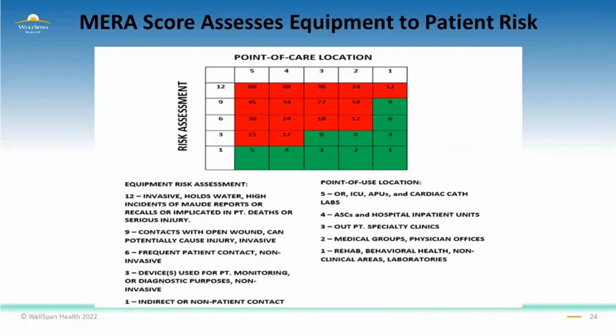We also know that the equipment is used in NICU, so we assign the location risk number as a 5. Now we take the two multiples, 12 times 5, and a score is borne out at 60, which is our highest MERA score, indicated in the red area of the grid. Any equipment lower than 12, which is 1 to 9, as I mentioned earlier, are considered to be lower risk.